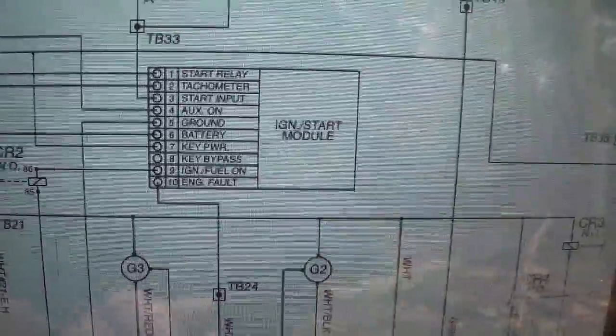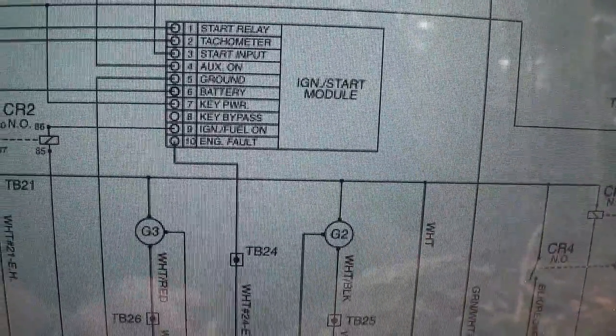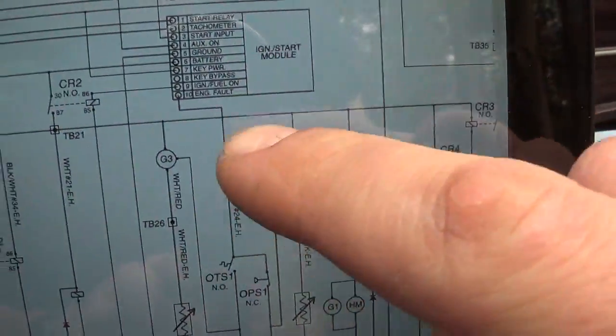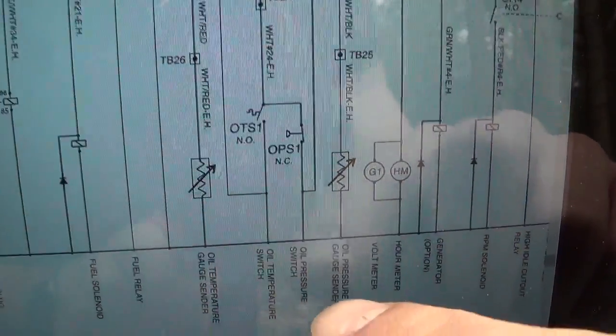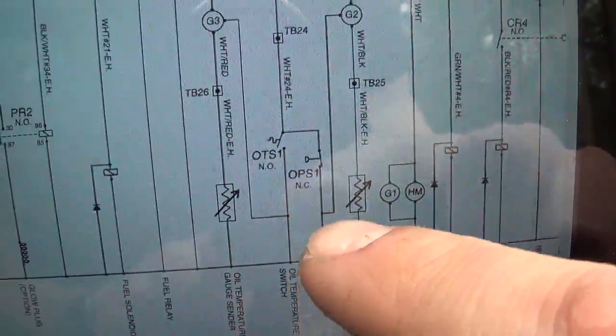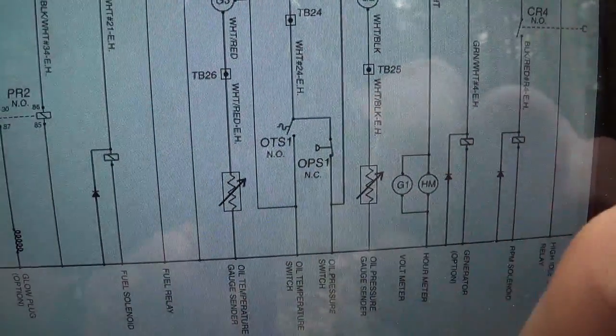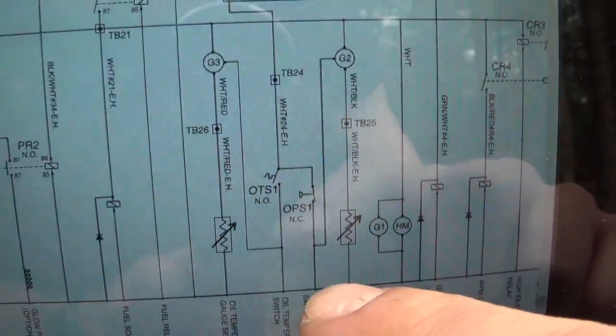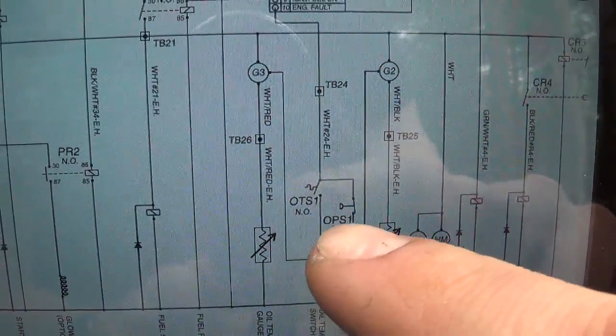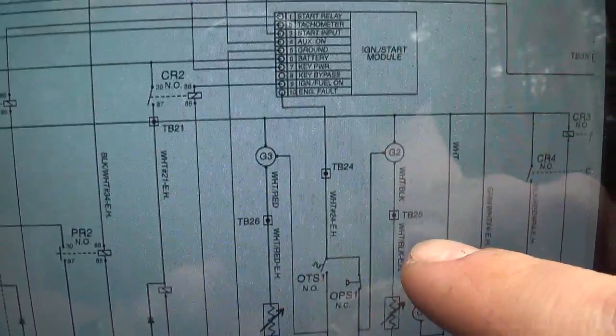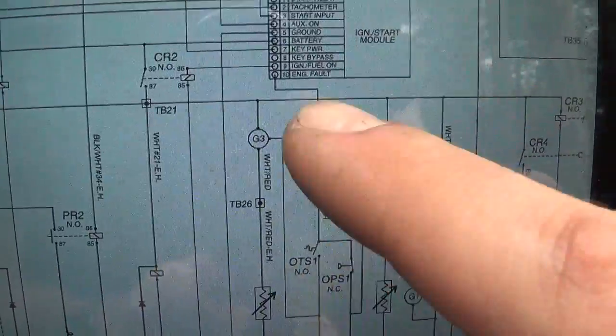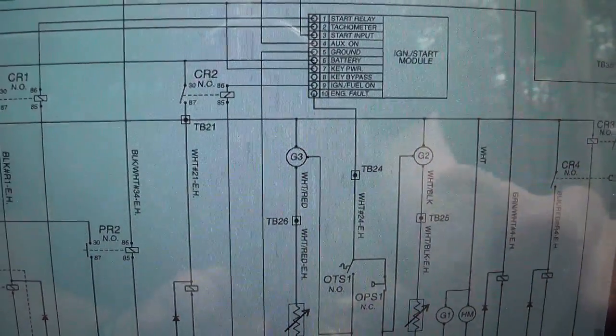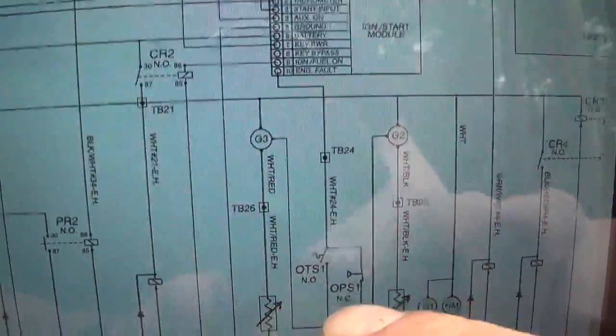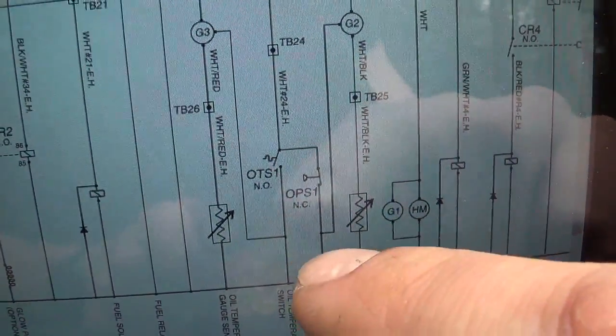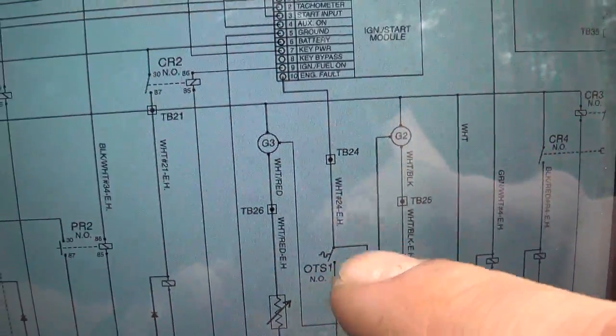So I'm assuming it needs a tachometer input, and definitely this engine fault, let's see what that does. There's an oil pressure switch, so that's normally closed, NC, and when this thing starts up, that probably opens, but if the oil pressure is too low, it closes, and then the start module shuts the thing off. So potentially could be this oil pressure switch for sure.